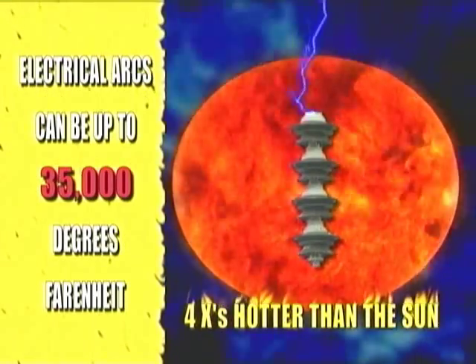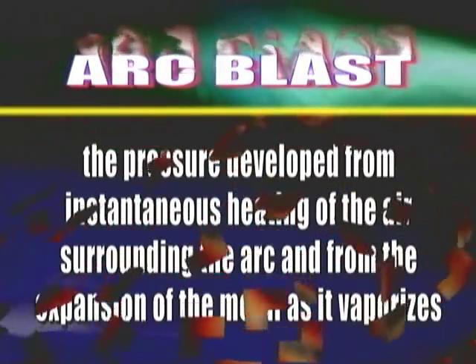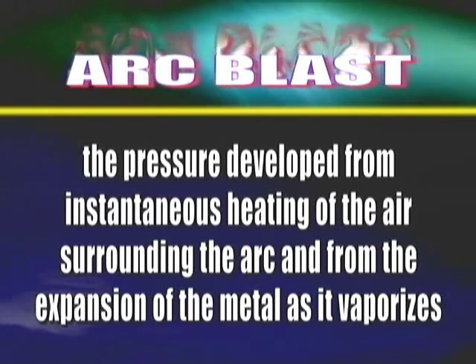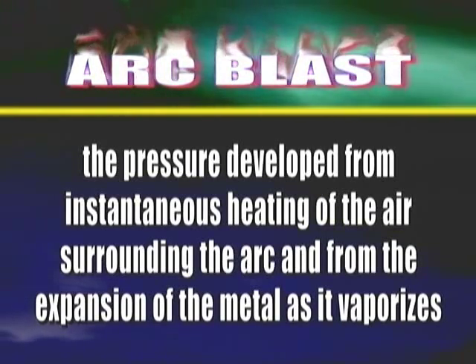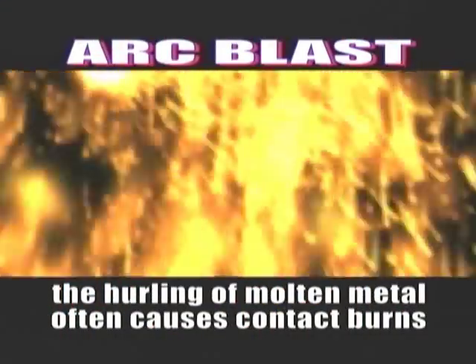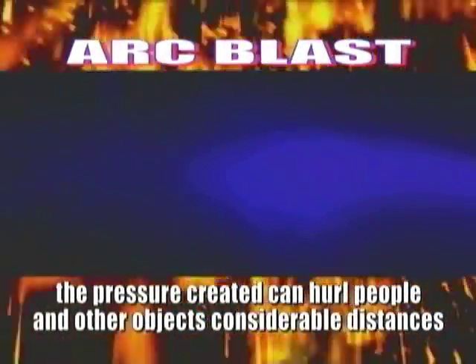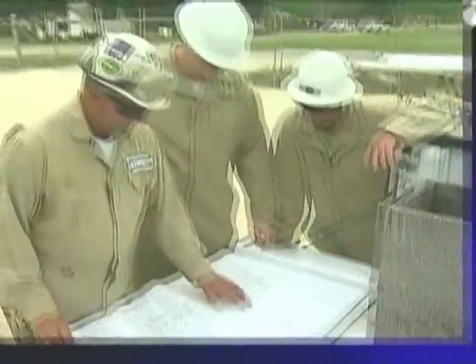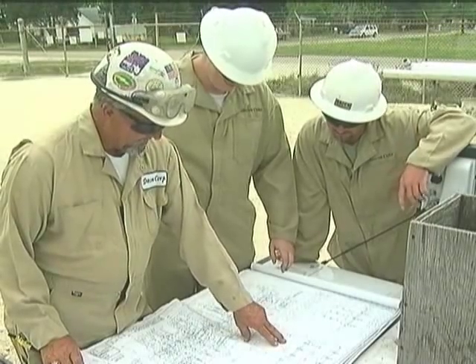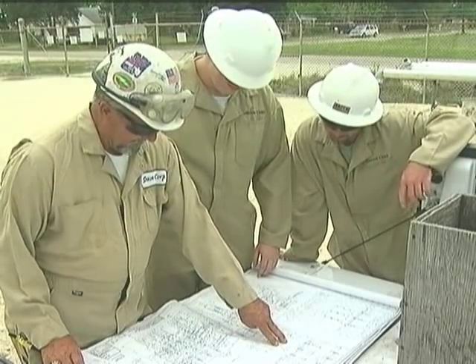Another burn type is an arc blast, which is the pressure developed from instantaneous heating of the air surrounding the arc and from the expansion of the metal as it vaporizes. The hurling of molten metal often causes contact burns, and the pressure created also can hurl people and other objects considerable distances. As a qualified worker, you must be able to identify parts that you may encounter.